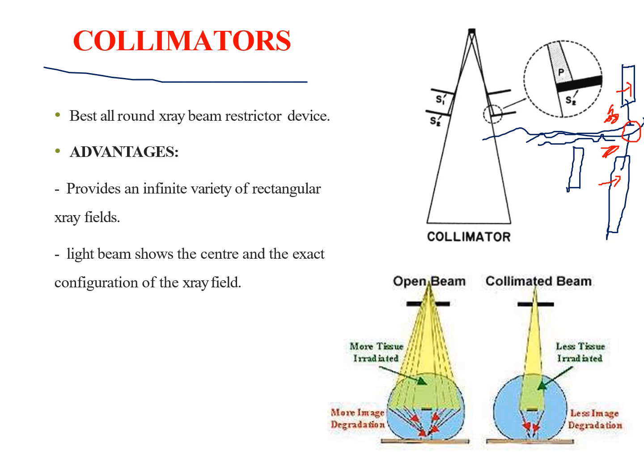This particular device uses a light to show the technologist the field to irradiate, and allows you to adjust the size and the area of your interest. See, by using this. Am I clear? Suppose you want a cone shape, just move the two shutters apart. Suppose you are placing them very close together, the area will be reduced. See here, a larger area to radiate; here, a smaller area to radiate.